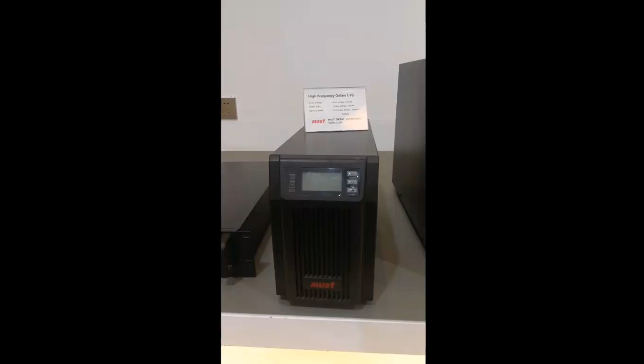Okay, next is the smaller one. It's also a high frequency online UPS. The input-output voltage is 220, and we have two options: battery inside or external battery. This smaller one is a 1 kVA UPS with a power factor of 0.9, so its actual capacity is 900 watt.